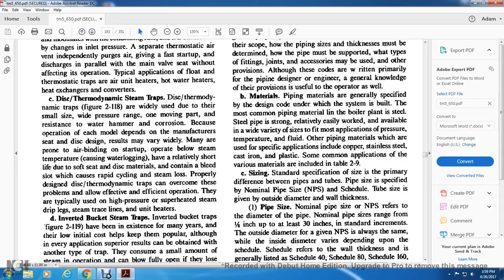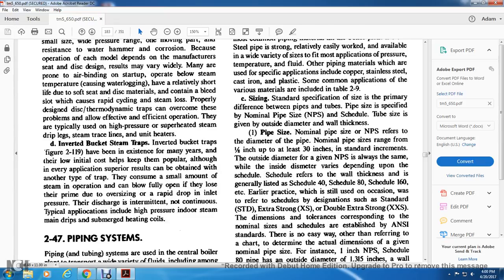Many are prone to binding on startup or operating below steam temperature, causing waterlogging, and will have a relatively short life due to soft seat and disc materials, and contain a bleed slot, which causes rapid cycling and steam loss. Properly designed disc and thermodynamic traps can overcome these problems. Although effective and efficient in operation, they are typically used with high pressure superheated steam drip legs, steam tracing lines and unit heaters.